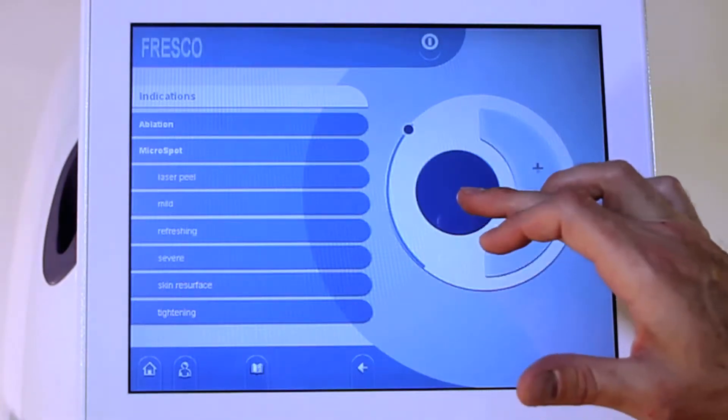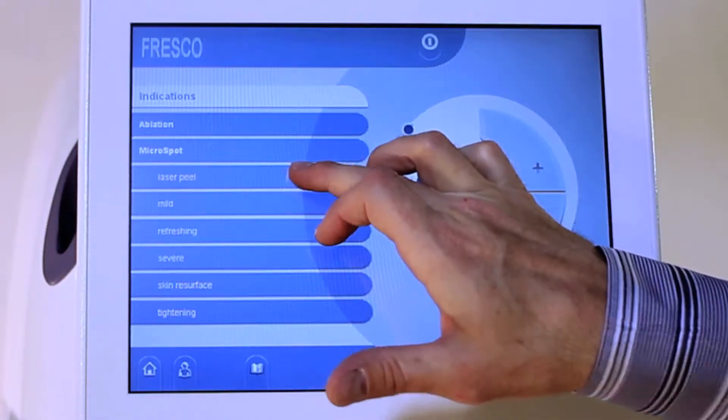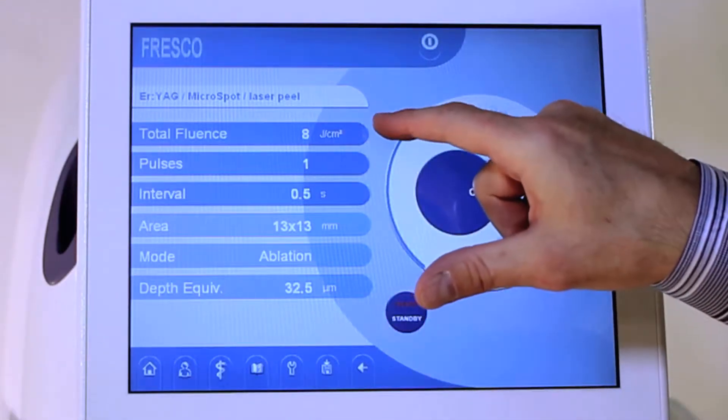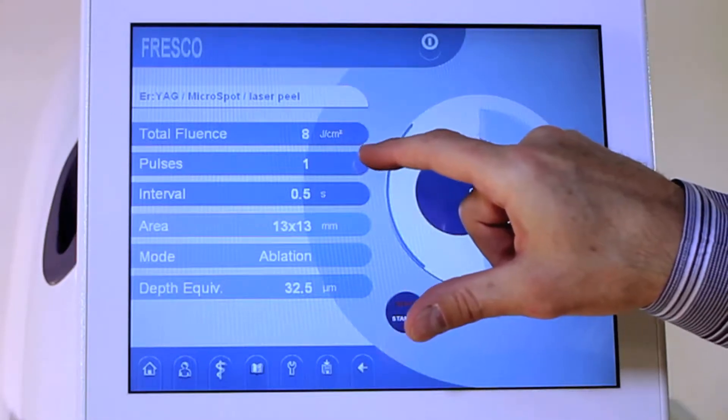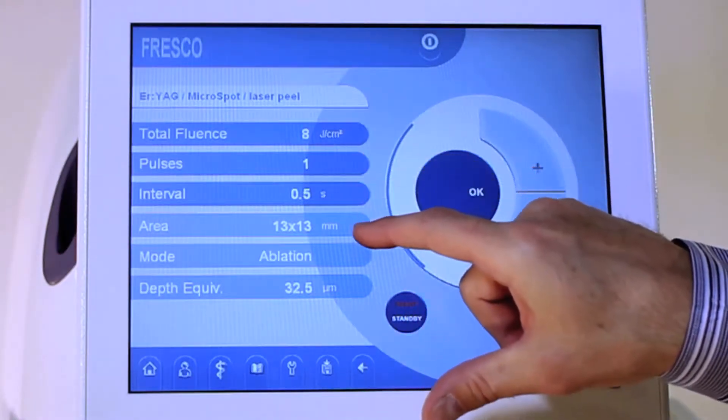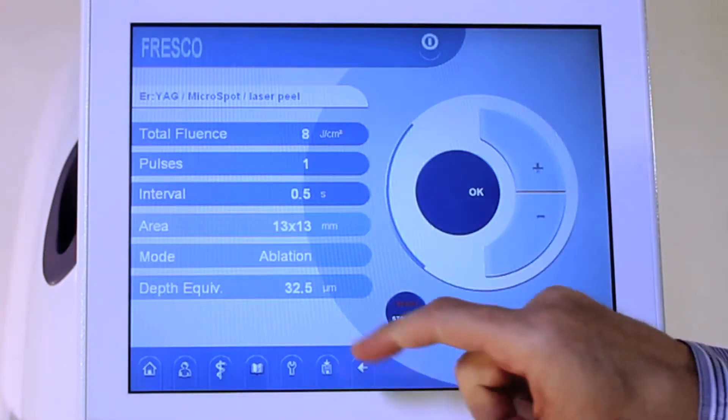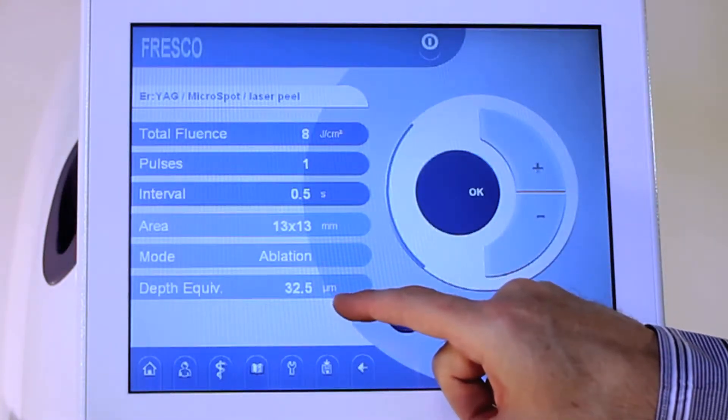When you want to adjust any one of these settings, you simply choose. It's going to give you your presets, and it will tell you your total fluence, the number of pulses, the interval between each pulse, your spot size at your treatment, which is a 13 by 13 fractional, and your depth equivalent.